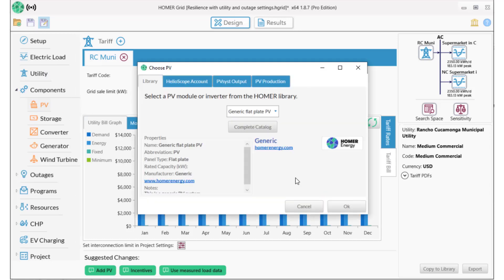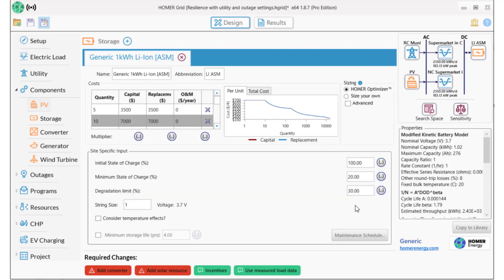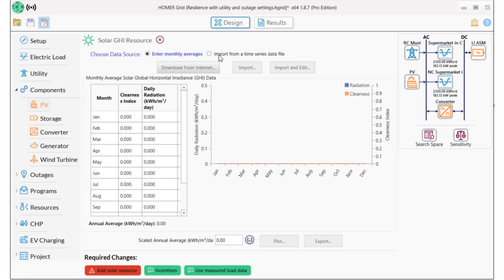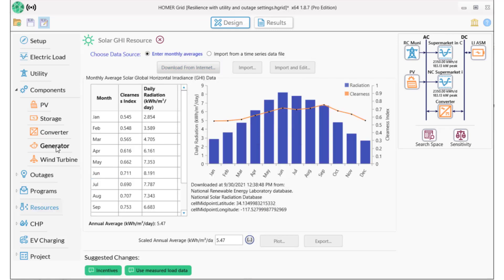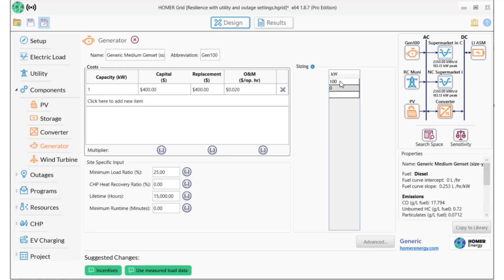Let's add the equipment we want Homer to consider. We'll add PV up to the 500 kW we can fit onto the roof, lithium-ion batteries, and a converter. Let's also add the solar resource using the NREL data. We need a genset that will be available during outages. I'll have Homer model gensets in 50 kW increments up to the peak critical load of 183 kW.